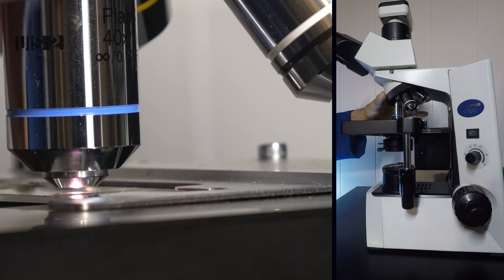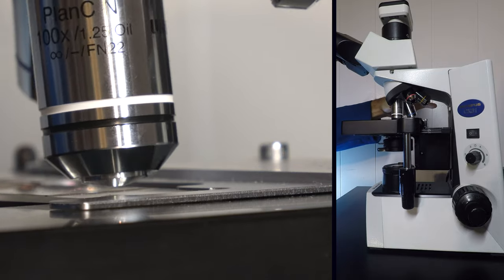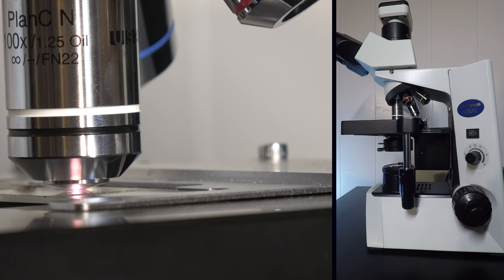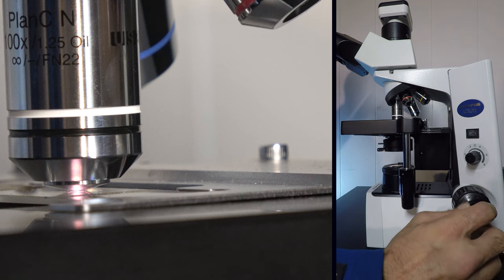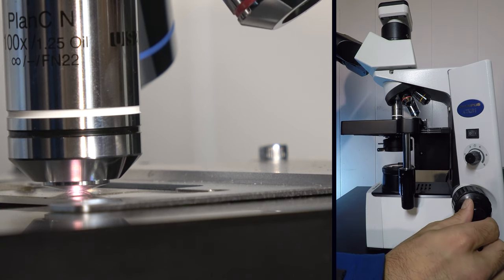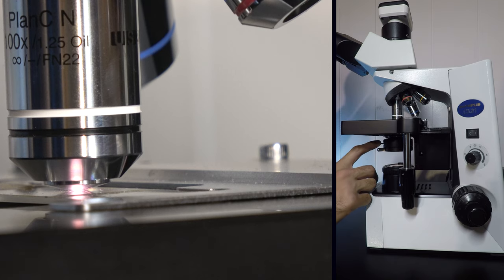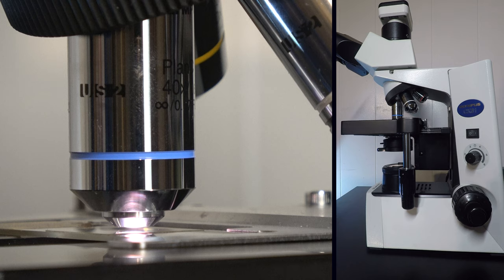The working distance with the 100x is minuscule. Pre-made slides with thin coverslips typically work well. If you've prepared a slide yourself with a thick sample or a thicker coverslip, then you may want to assess whether the 100x objective will move into place without contacting the slide before adding oil.